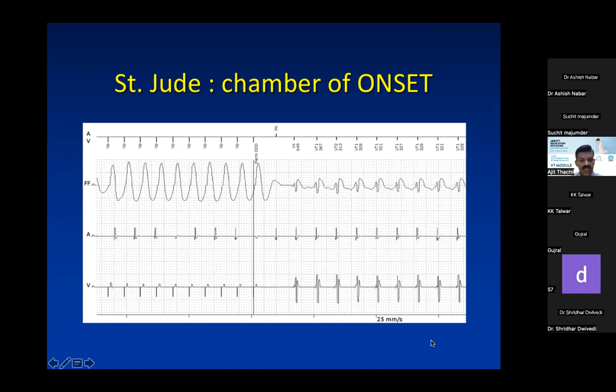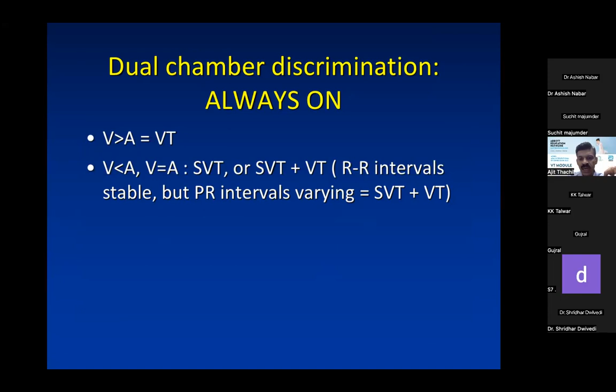Dual chamber discrimination is always on, and this is what it says. V more than A is VT; V less than A, or V equals A, is SVT; or it may be SVT plus VT. That is, the RR intervals are regular, but the PR intervals are different. This means that the atrial rate is different from the ventricular rate. It will call it SVT plus VT. But there is a problem here with dual chambers. For example, look at this tracing. This is an atrial sensing. There is a ventricular pacing, and you can see another deflection in the atrial channel corresponding to the ventricular sensing.